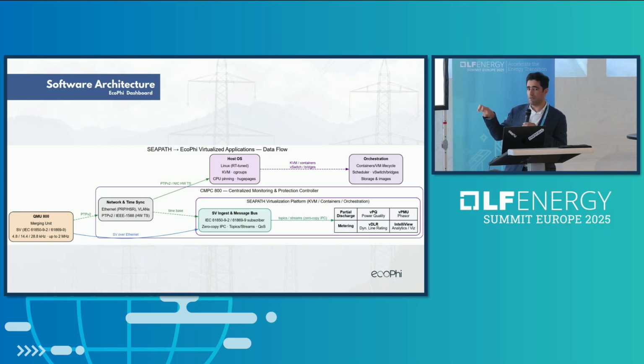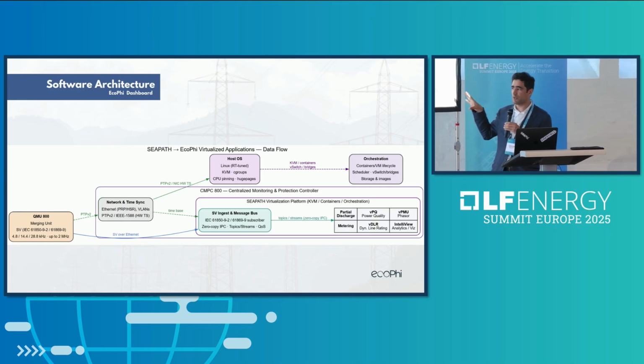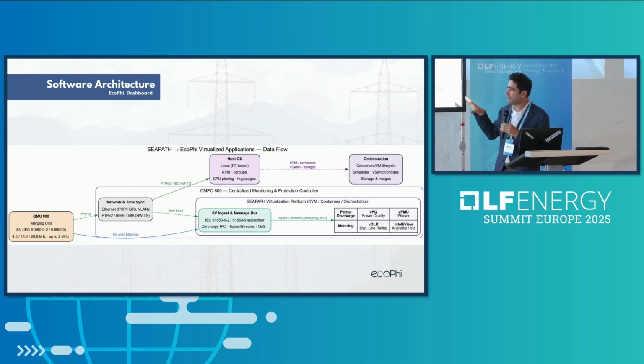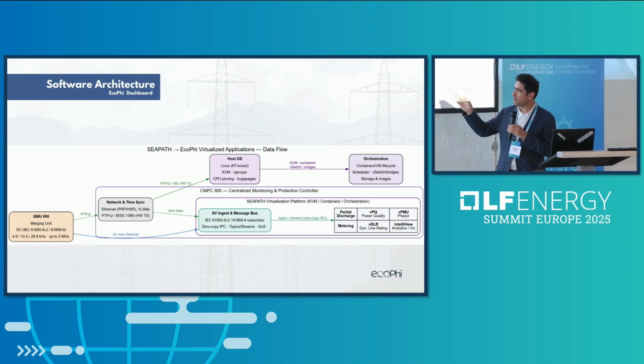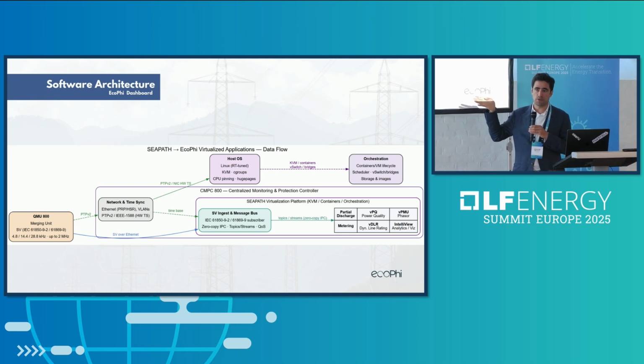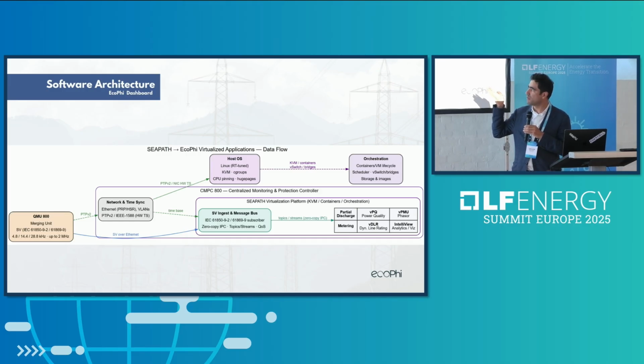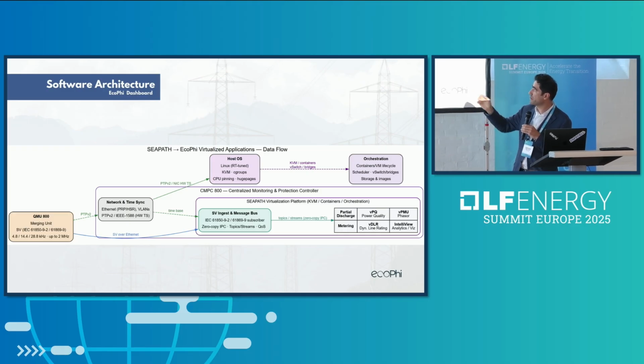This is even more detail on how the system works. Basically, the QMU 800 can publish sample values at optional rates of 4.8, 14.4, or 28.8 kilohertz, any sample value you want, even up to 2 million samples per second. There is no limitation there, according to IEC 61869.